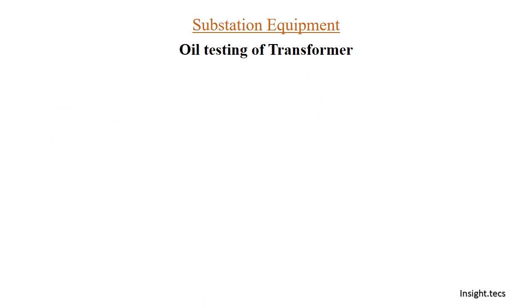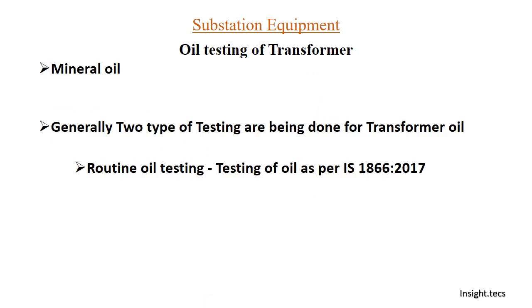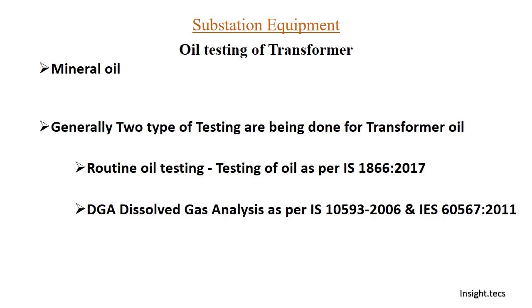For mineral oil, there are generally two types of testing for transformer oil. The first is called routine oil testing, done as per IS standard 1866:2017. The second is dissolved gas analysis (DGA), done as per IS standard 10593:2006 and IS 60567:2011.